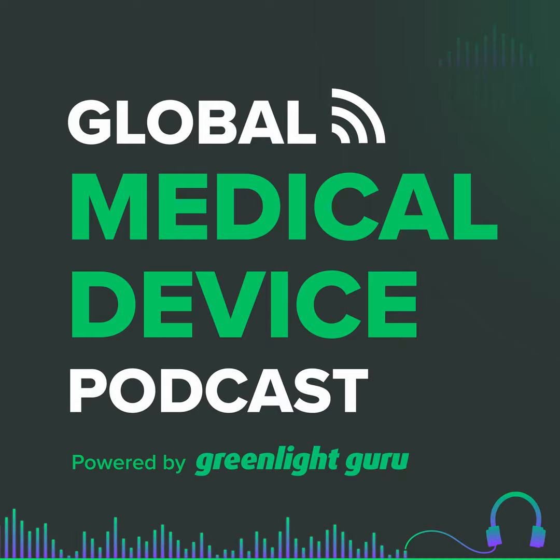You run through that, and then, does this protocol contain subjects which are vulnerable? Yes or no? And what does that mean? Well, it means this and this and this. And how critical is it for the outcome of the protocol? Does it influence the patient, the user, and third-party users? And how can we mitigate that? So you see, the process is, in a very simplified way, what we do in a risk assessment on the product. The thinking process is the same, but the questions are just slightly different.